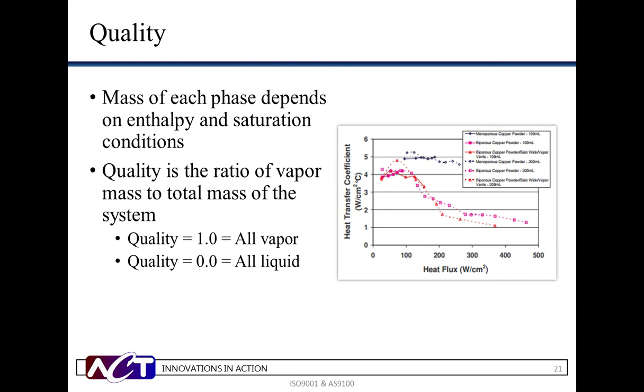There is an optimum quality range, or sweet spot, for two-phase systems. When the system is entirely vapor, the quality equals 1. When the system is entirely liquid, the quality equals 0. A quality that is too high will result in flow instabilities. However, a quality that is too low will sacrifice your heat transfer coefficient, and by extension your heat flux capability as well. Although all of these challenges are significant, technology has been designed to overcome each one.